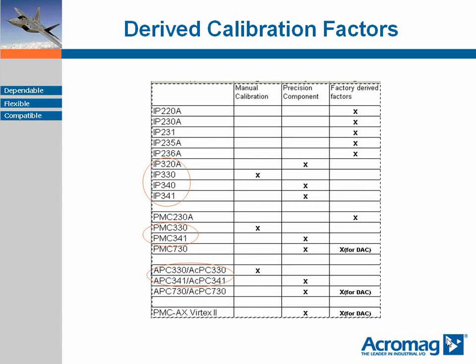Boards numbered in the 300s are analog input boards. They are all designed with an on-board circuit which creates a reference voltage level predefined in the manual depending on the gain and voltage range. This voltage can be read at any time in the user's system and becomes an essential factor in the calibration equations referenced in a previous slide.